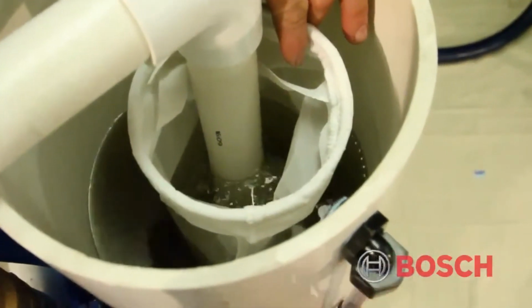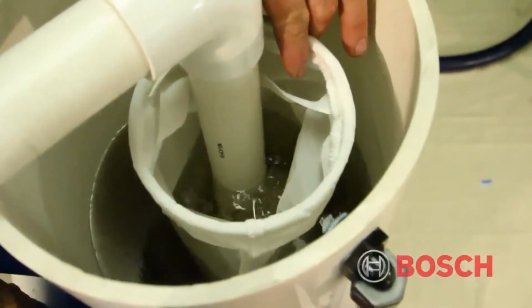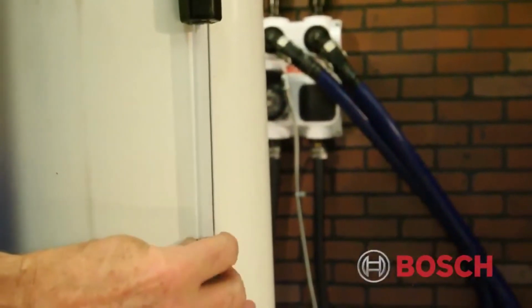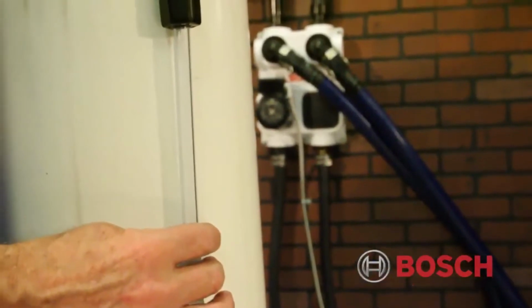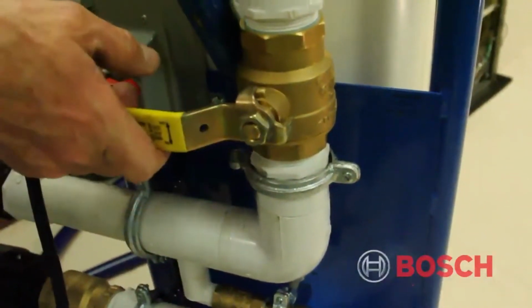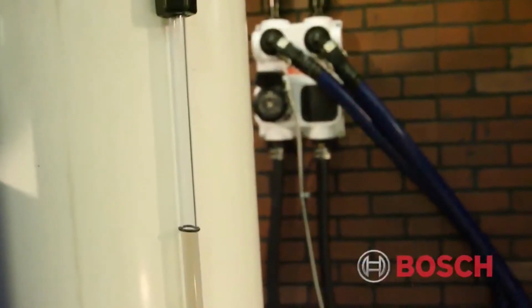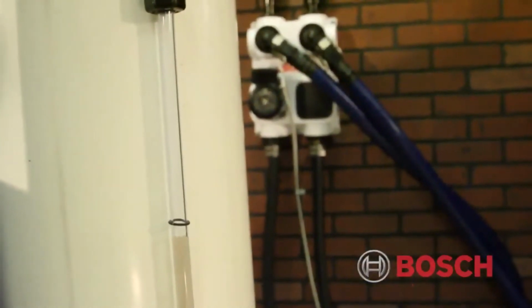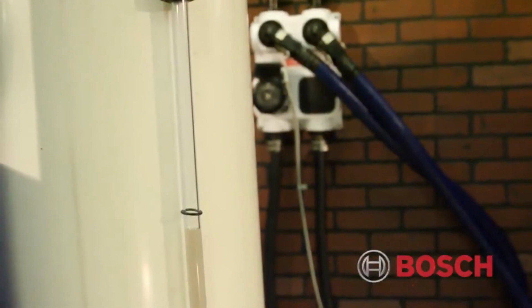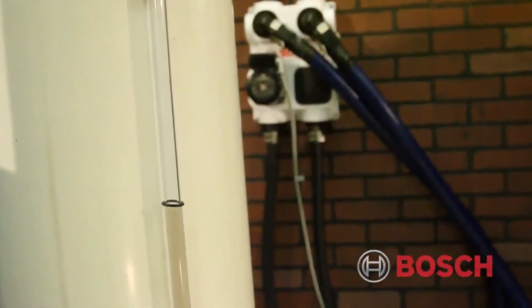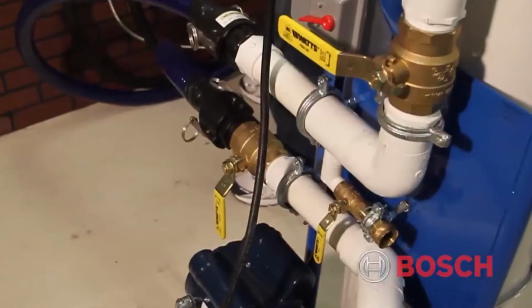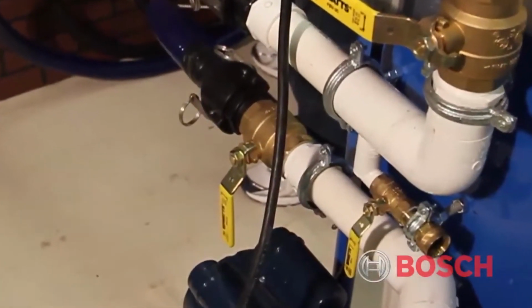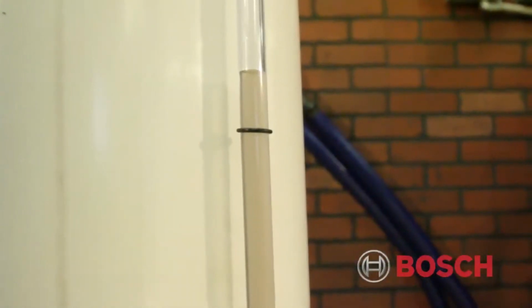To verify possible air pockets in loop field, a deadhead process is necessary. But before we do this, mark the level of the water by adjusting the black ring on the reservoir sight glass tube. Start the deadhead process by closing the 1.5-inch flush cart return valve and monitoring the fluid level. If the fluid drop is greater than 1 inch, there is still air in the system that is being compressed by the power of the pump. Reverse the flow path or open and close the flush cart discharge valve to shock the flow and continue flushing purging activity. Continue filling and deadheading until the fluid drop is less than 1 inch.